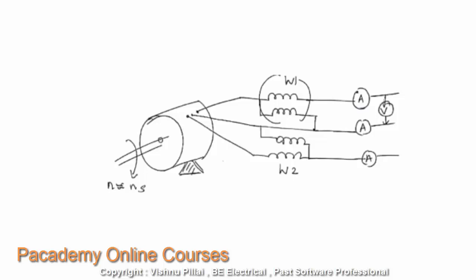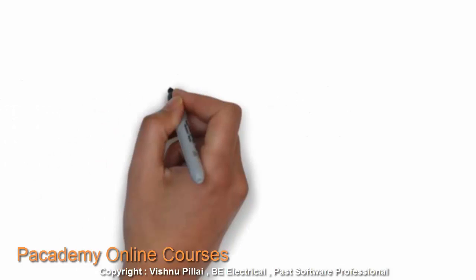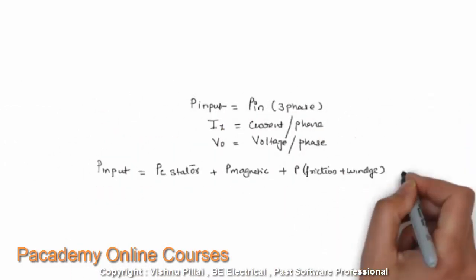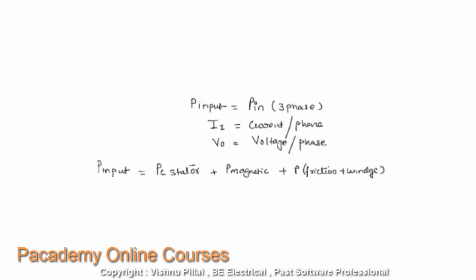This is the arrangement of the no load test. Like the no load test in a transformer, the shaft is not connected to any load — no mechanical work is delivered — and it is free to rotate. The three-phase power is measured using the two-wattmeter method, the current in each phase is measured using an ammeter, and the supply voltage is measured using a voltmeter. I1 is the current per phase and V0 is the no load voltage.